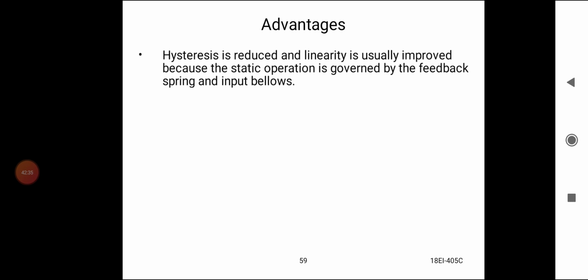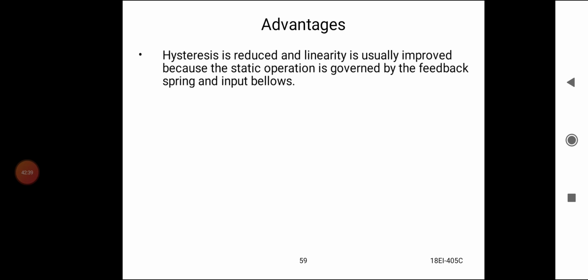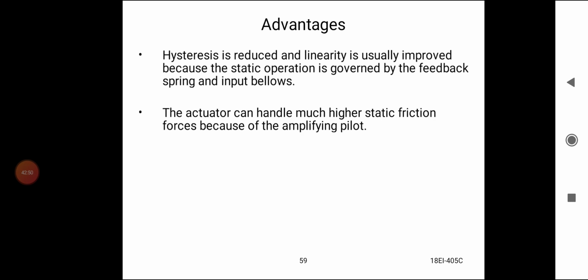Advantages: hysteresis is reduced and linearity is usually improved because the static operation is governed by the feedback spring and input bellows. The actuator can handle much higher static friction forces because of the amplifying pilot.